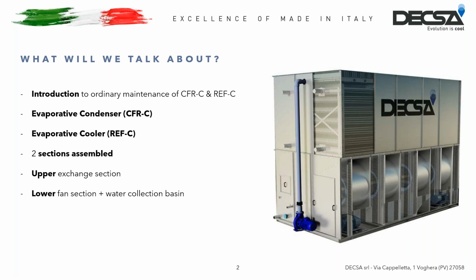For example, if we talk about a plant that goes to serve the conditioning of a hospital or a shopping center, the cooling tower is operational for about 8 months per year. So the remaining period can be used to carry out all the checks and the extraordinary maintenance, you know. If the tower is a part of an industrial plant operating 12 months per year, a few consecutive days of downtime are usually expected to carry out maintenance activities. But it would be good to organize to have a few more hours outside the expecting downtime.